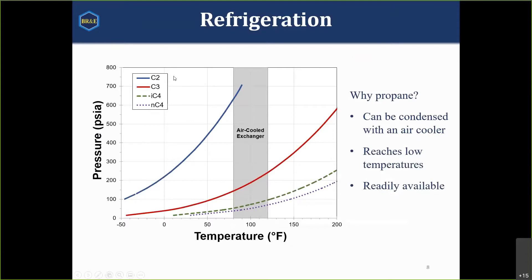Why do we use propane? We could use ethane, ethylene, isobutane, or normal butane. Looking at the pressure-temperature diagram for ethane, propane, isobutane, and normal butane — since these are pure components, the phase envelope collapses to a straight line, essentially the boiling pressure for any given temperature. The condenser temperature is largely set by outdoor conditions; most of the time the condenser is an air-cooled exchanger, and air coolers will get you down to about 80 to 120 degrees Fahrenheit — in Texas it's probably closer to 120.